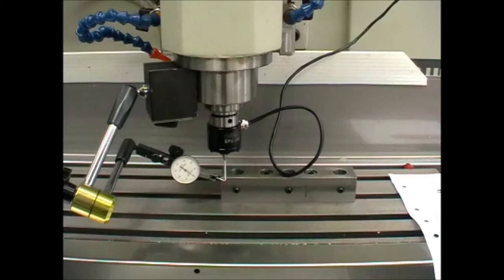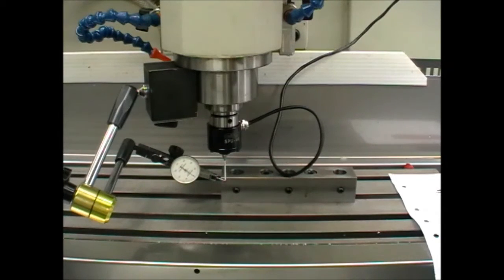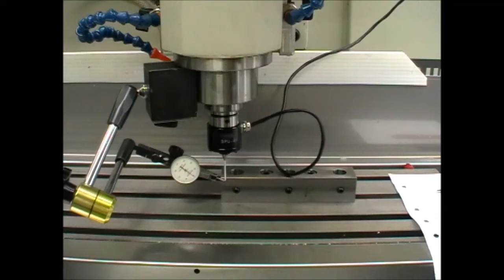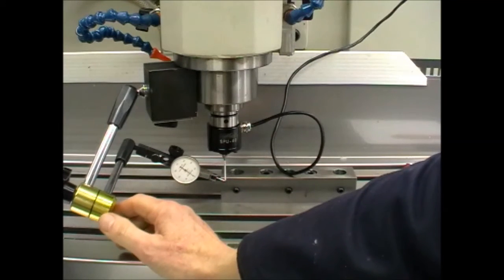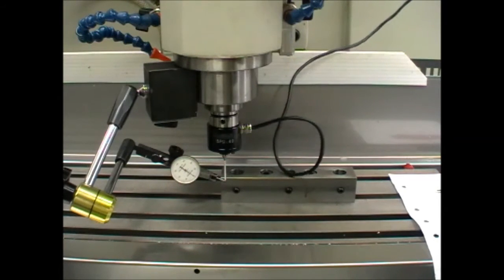Some of you won't be aware of this, but it takes about 109 grams for the electrical trip to take place in one direction and in another direction nearly 150 grams. This is a quick way to demonstrate the error. I've set the ball on the end of the stylus running true. You can see the dial indicator is in contact—that's a hundredths of a millimeter dial indicator.